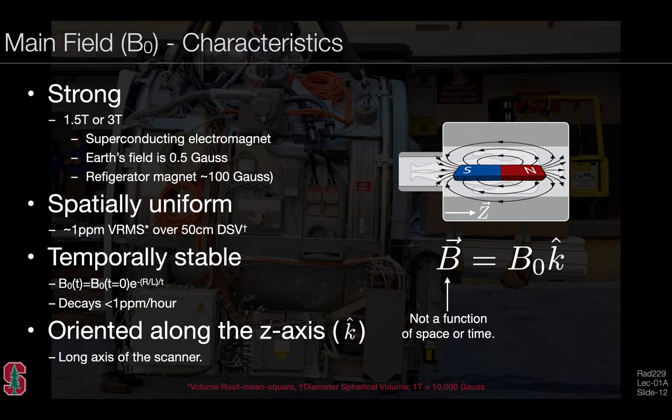The B0, or main field, has several important characteristics. First, it's a very strong magnetic field—1.5 Tesla or 3 Tesla for most clinical imaging systems. It is a superconducting electromagnet. In reference to the Earth's field, which is about half a gauss, or a refrigerator magnet at about 100 gauss, this is an extremely strong electromagnetic field. It is spatially uniform, varying by only about one part per million RMS over a 50 centimeter diameter sphere. It's also temporally stable, decaying very little as a function of time, perhaps one part per million per hour. It's oriented along the Z axis, the long axis of the scanner, generally along which the patient's head and foot is oriented.